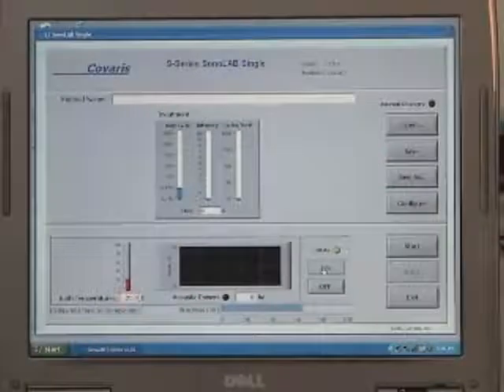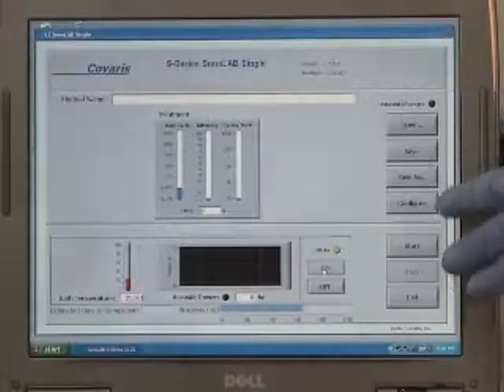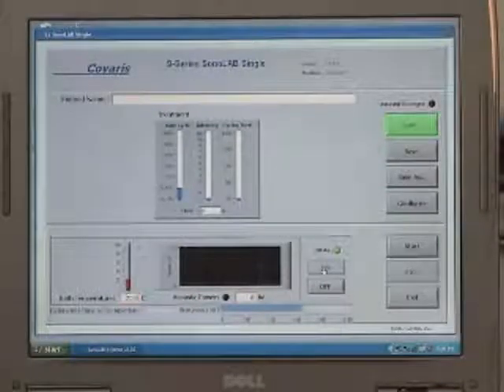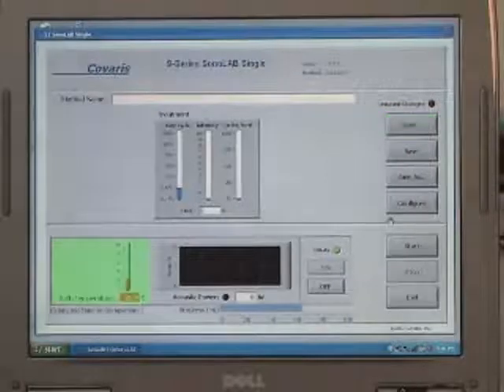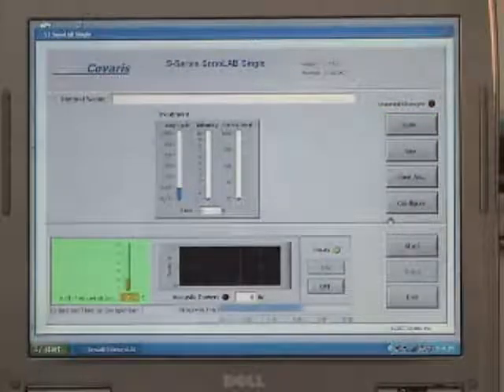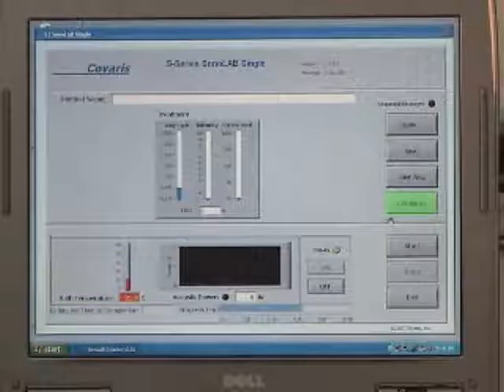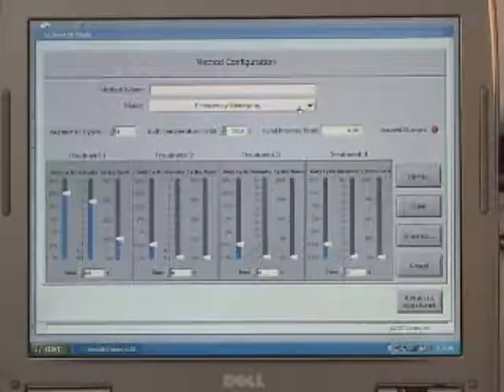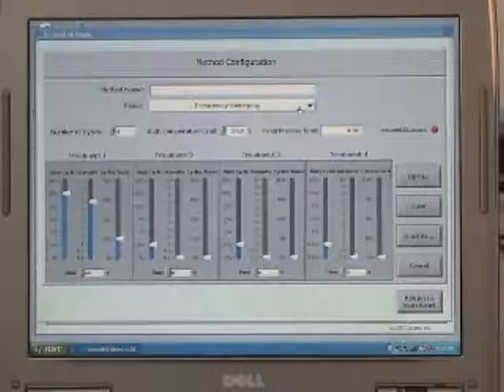The general operating controls are located down the side. For example, Open selects a previously saved method. The current water bath temperature is displayed in the lower left corner. To create your own method, select Configure. Clicking on Configure opens the configuration panel where specific treatment parameters are selected. Here is where you can create, modify, or save a method.